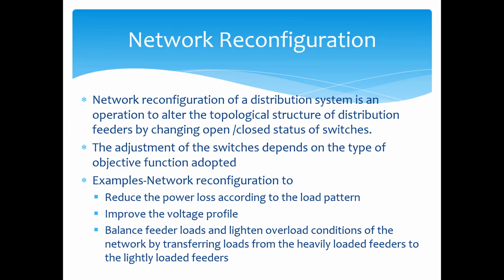If we find that when we supply power from a particular direction the network voltage levels are going down, we can feed the network from the other direction, or we can shorten the feeder length. We can shorten one feeder and extend another. So I think you can understand what I mean. If it is in a ring, for the low voltage side we can reduce the feeder length by switching off one section and adding that section to a feeder which has a good voltage profile.